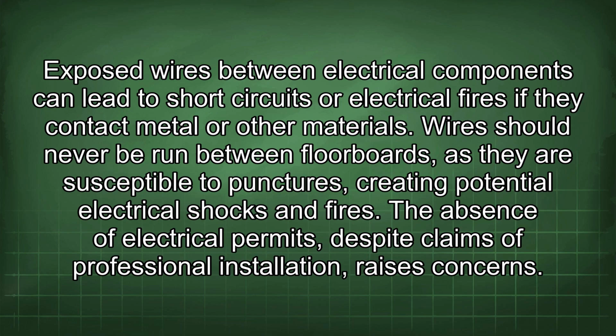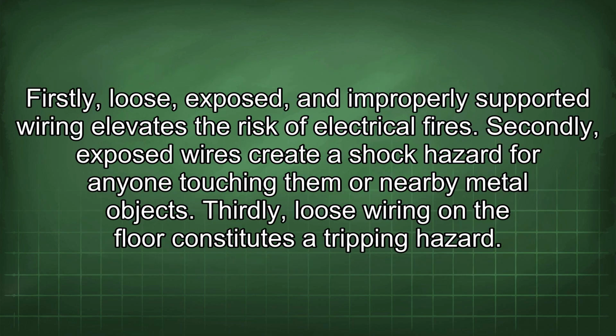Wires should never be run between floorboards, as they are susceptible to punctures, creating potential electrical shocks and fires. The absence of electrical permits, despite claims of professional installation, raises concerns. Firstly, loose, exposed, and improperly supported wiring elevates the risk of electrical fires. Secondly, exposed wires create a shock hazard for anyone touching them or nearby metal objects. Thirdly, loose wiring on the floor constitutes a tripping hazard.